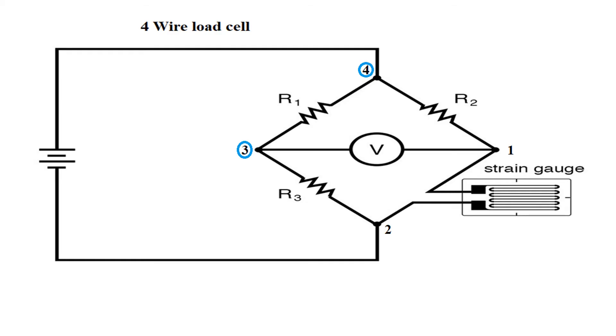A multimeter will be used to measure the resistance of the load cell. From the load cell data sheet, for example, the resistance of the strain gauge will be 350 ohms when there is no load.